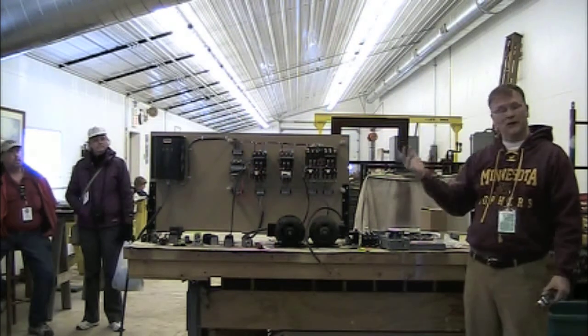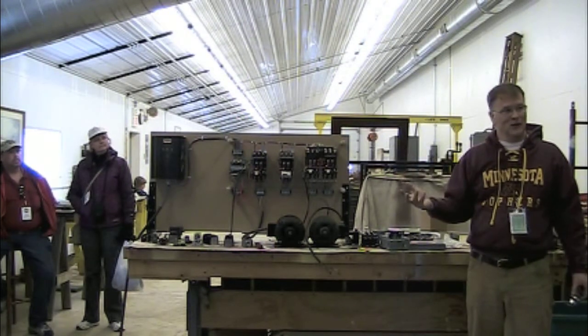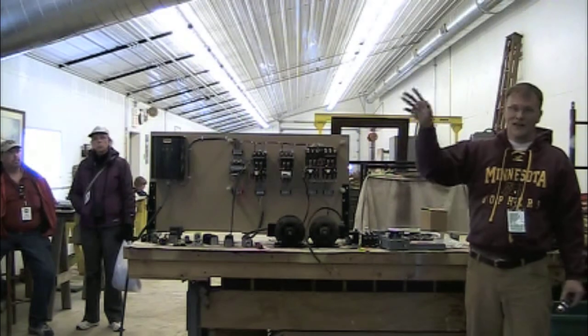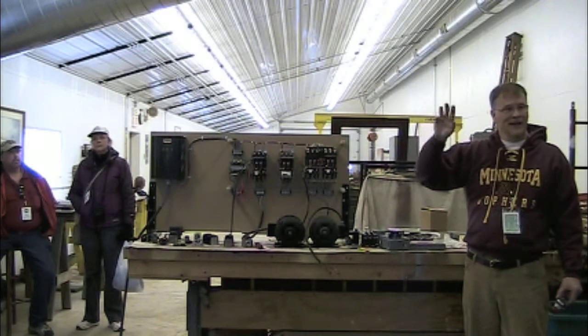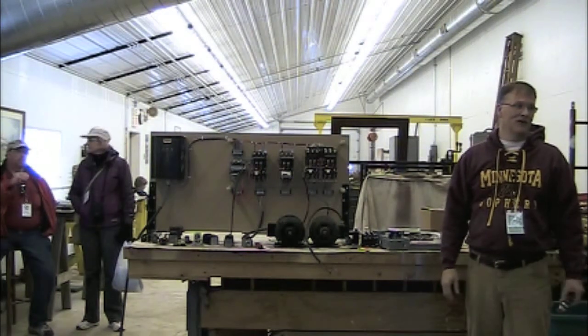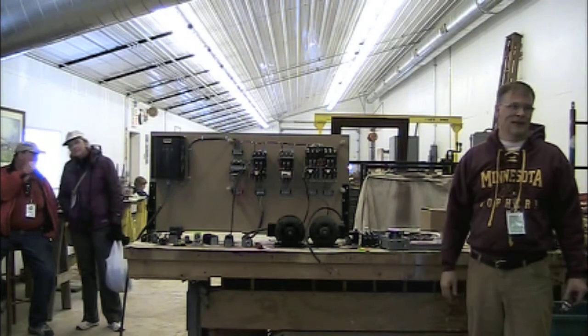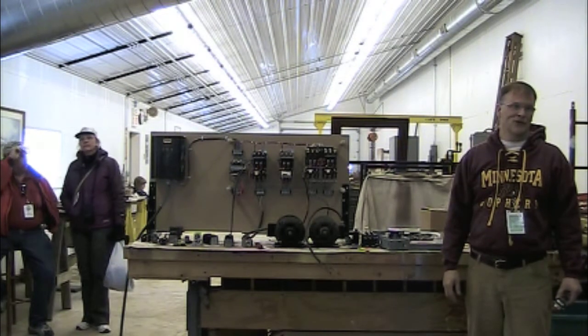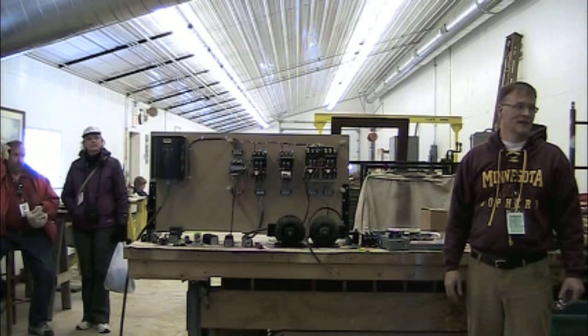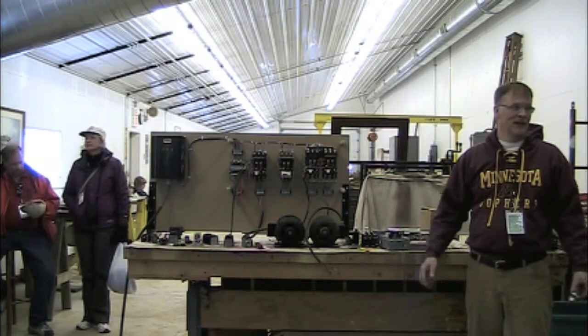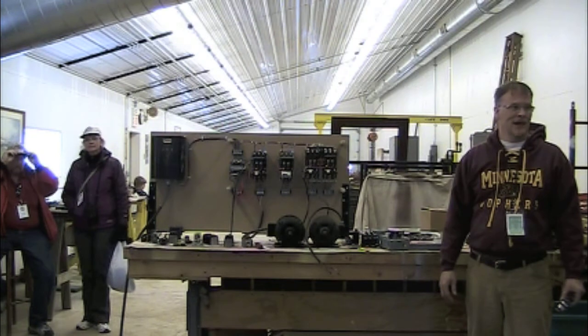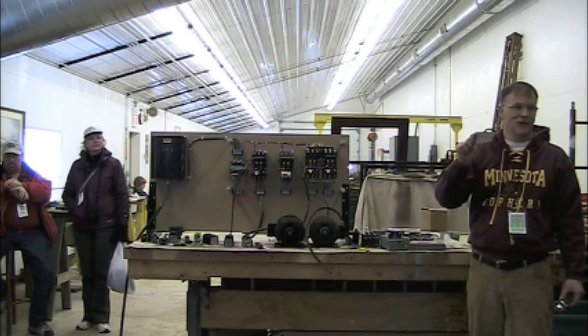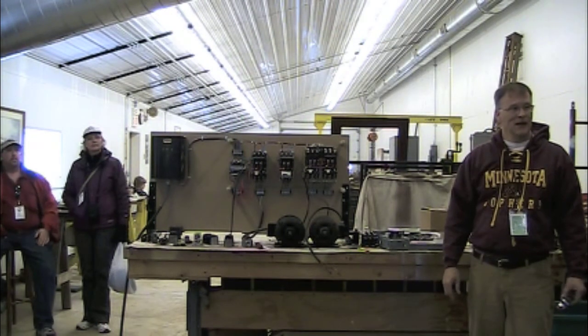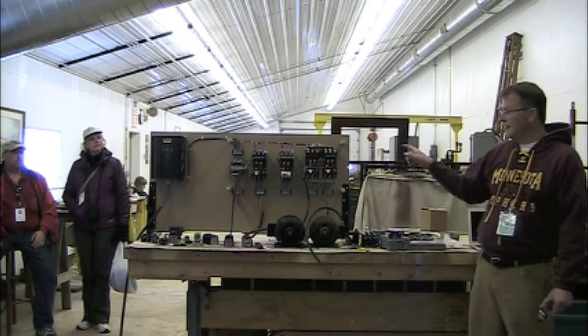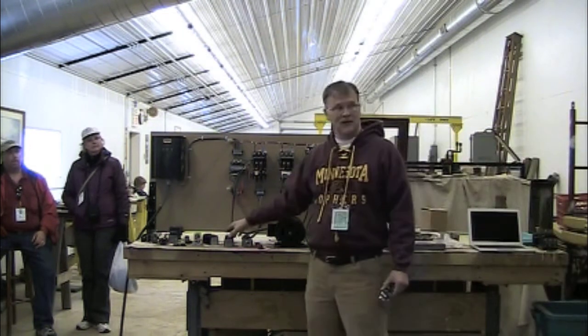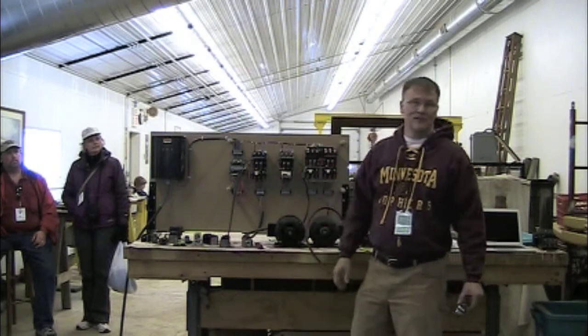And 120 volt is very common because in the industrial world, OSHA follows other guidelines, and you're limited to having 120 volt at the operator. So 120 volt and control transformers are much more prevalent in the industrial world, because with anything new you can't have 240 or 480 volts at the push button. But if you're running a 480 volt coil, you've got 480 volts going out to this.